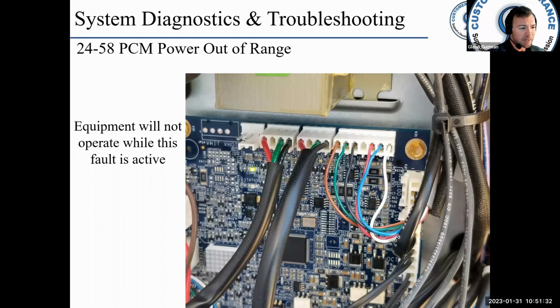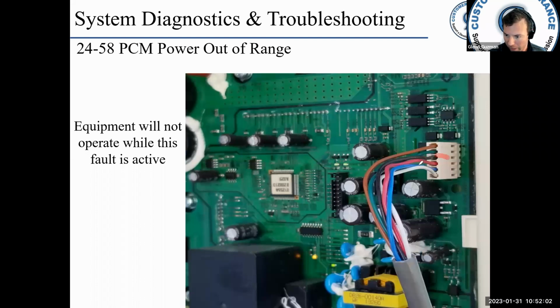So we need to verify the PCM is providing 5 volts DC to the VFD by checking pins 3 and 4, which are the black and red right here. And let's see, red and black. Okay, we want to check for 5 volts DC there. You want to check it coming out of the PCM and going into the VFD. Okay, you want to make sure you have that voltage all the way up there. Here's red and black here. You can check it.